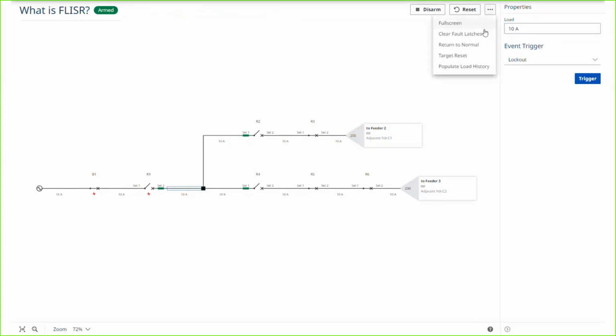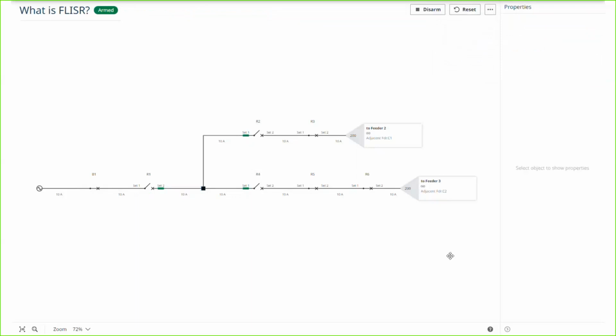Now, I would like to return my circuit to normal. So I have this outage. I've gone out, I've repaired the fault, and I would like the circuit to go back to the way it was before the fault actually occurred. In this case, I am having FLISR close the recloser for me. Most procedures you would close that recloser manually, make sure that it held, that the fault was truly repaired, and then optionally allow FLISR to return the rest of the circuit to normal. That would work as well.